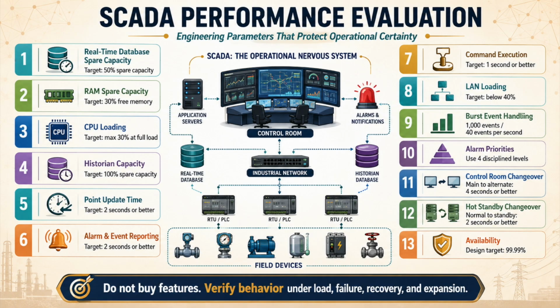Do not evaluate SCADA systems by appearance. Evaluate measurable behavior under load, failure, and recovery. Do not trust maximum tag counts without scan rate, alarm load, historian rate, client count, and redundancy context. Do not size servers from minimum hardware recommendations, because minimum hardware starts software, while performance hardware sustains operations. Do not treat historian sizing as storage arithmetic, because historian performance includes write rate, query speed, retention, compression, archive, backup, and recovery. Do not confuse redundancy with availability, because redundancy is a component feature, while availability is a complete system result.